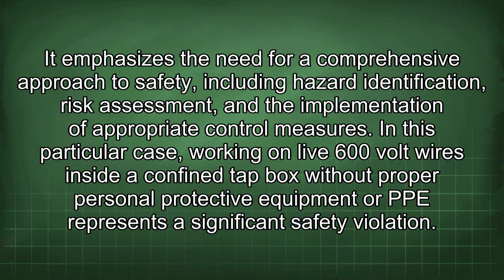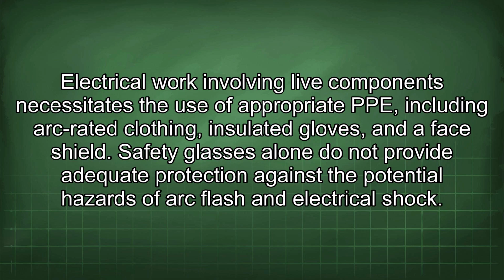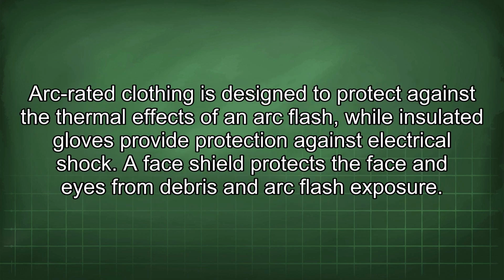In this particular case, working on live 600-volt wires inside a confined tap box without proper personal protective equipment, or PPE, represents a significant safety violation. Electrical work involving live components necessitates the use of appropriate PPE, including arc-rated clothing, insulated gloves, and a face shield. Safety glasses alone do not provide adequate protection against the potential hazards of arc flash and electrical shock. Arc-rated clothing is designed to protect against the thermal effects of an arc flash, while insulated gloves provide protection against electrical shock. A face shield protects the face and eyes from debris and arc flash exposure.